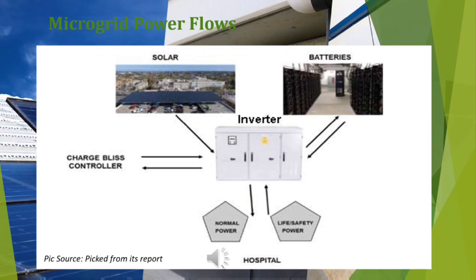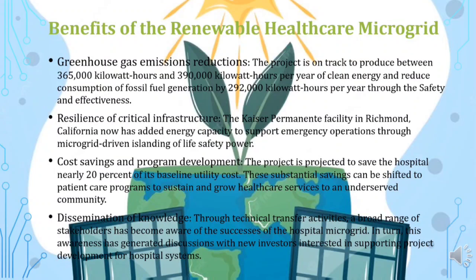At night, the PV converter section shuts down to conserve battery energy and minimize losses. The inverter requires the battery to provide islanded power. If the battery disconnects or shuts down, the inverter will too. Benefits of the renewable energy microgrid.